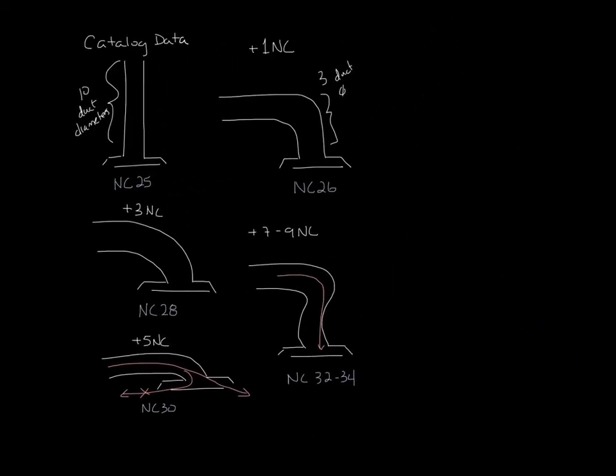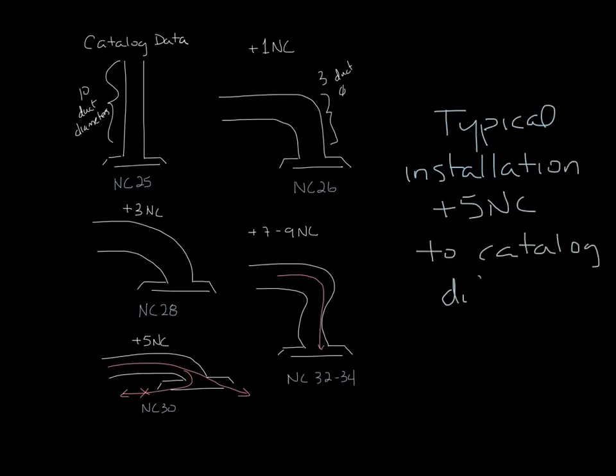So let's scoot this over so we can bring all of these installations back on screen. Different types of diffusers are affected differently, but these are good rules to use. A typical installation will probably add about 5 NC to cataloged diffuser data. So you should take that into consideration when selecting diffusers.